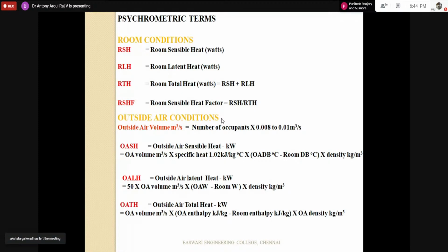For example, in a theater the number of occupants will be more, so the amount of outdoor air you have to take in for ventilation should definitely be high. When the outdoor air comes from outside into the conditioned space, it will bring outdoor air sensible heat. What is the meaning of that? You have an indoor room dry bulb temperature and an outdoor air dry bulb temperature. The difference between them is the sensible heat component, that is m Cp delta T only. Volume and density multiplied give mass, then specific heat and the delta. That delta is the outdoor air dry bulb temperature minus the room dry bulb temperature. This m Cp delta T gives the outdoor air sensible heat component.